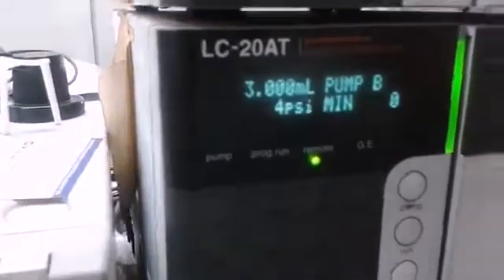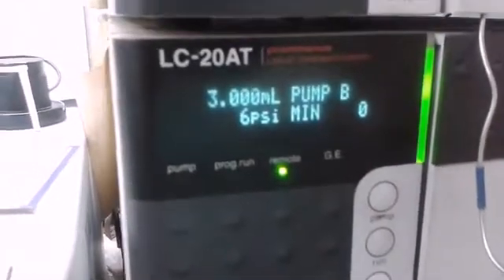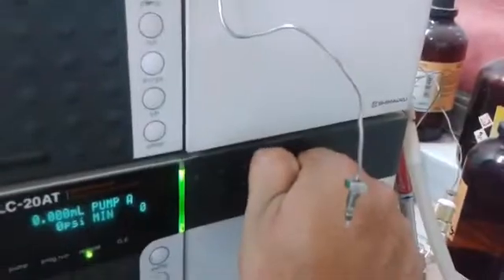Now you come to this side, the purging has been completed. See, 3 ml pump B, 6 psi. Here also 0 ml pump A, like that it has come. Leave that one. You tighten your knob clockwise. This also, tighten your knob clockwise.